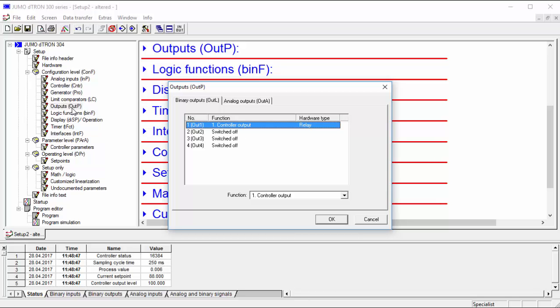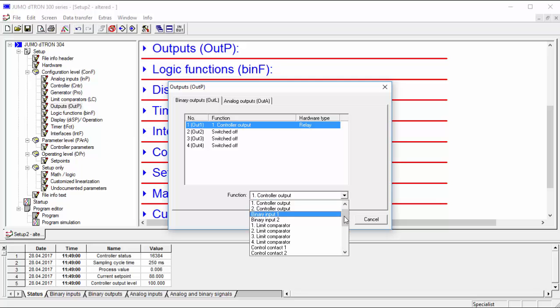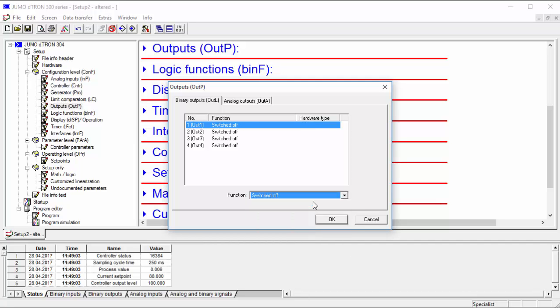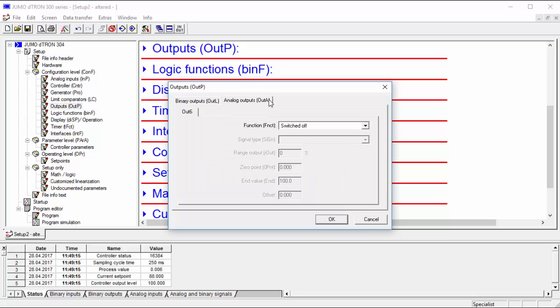The first controller output is assigned to the first binary output as standard. This output is deactivated when using the continuous controller. For the continuous controller, the first controller output is assigned to the analog output. Here, this is output number 6. The signal is 4 to 20 milliamp for an output level of 0 to 100%.